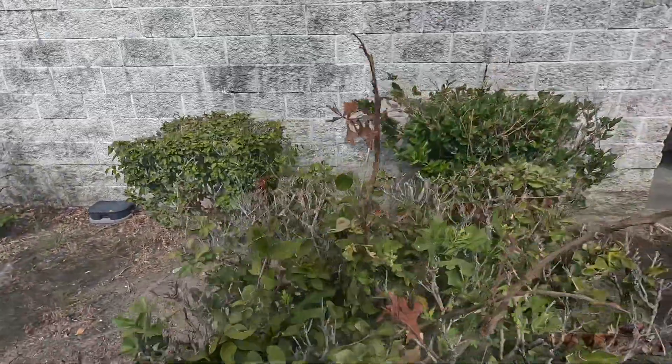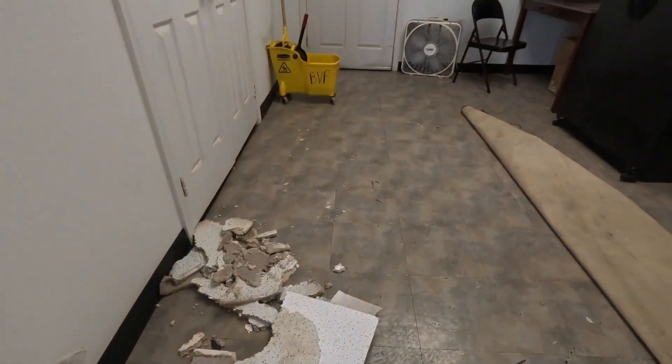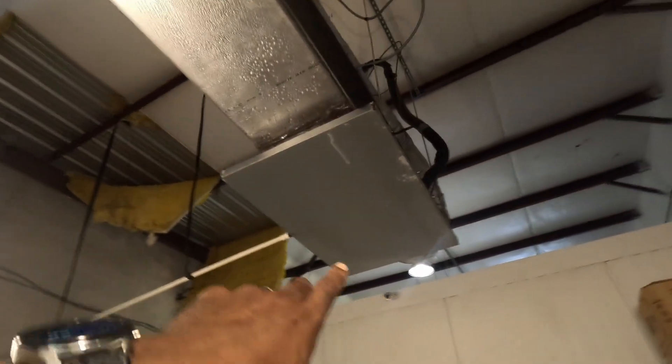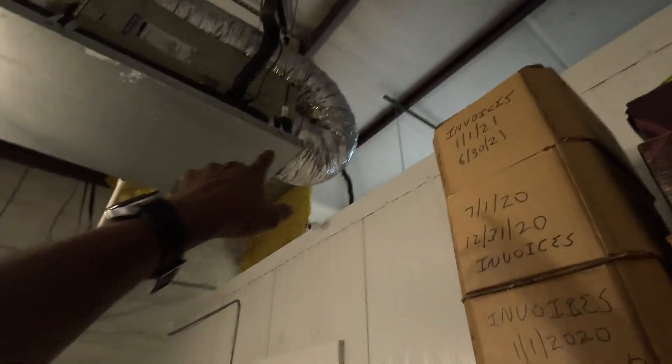Let's see what's going on on the inside. Either we got a broken pipe dripping out the ductwork. We're trying to get a ladder. I'm suspecting that's the secondary drain pan right here — that's what you see leaking outside. But I did not see a primary at first. Wait — okay, that's the primary right there.